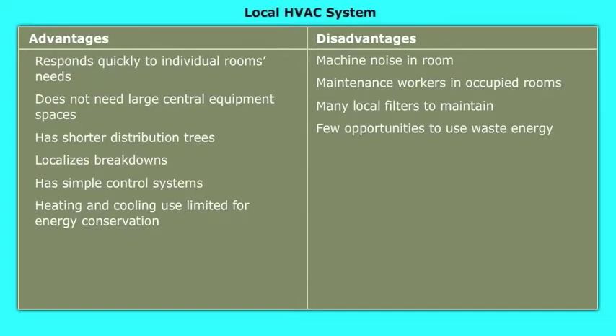Advantages of a local HVAC system include: responds quickly to individual rooms' needs, does not need large central equipment spaces, has shorter distribution trees, localizes breakdowns, has simple control systems, and heating and cooling use is limited for energy conservation. Disadvantages include machine noise in room, maintenance workers in occupied rooms, many local filters to maintain, and few opportunities to use waste energy.